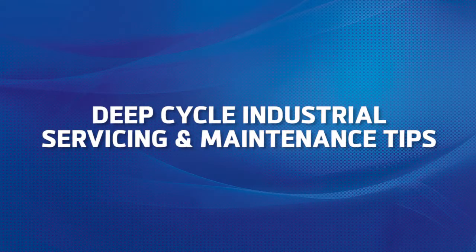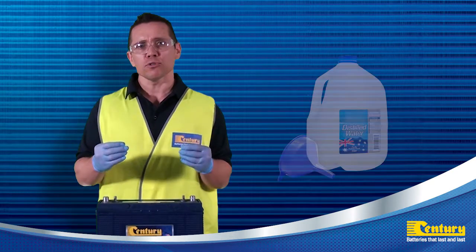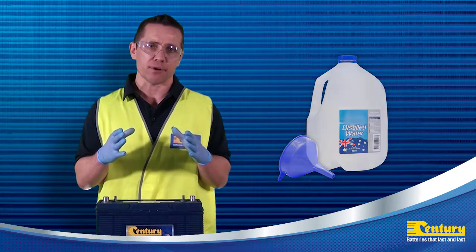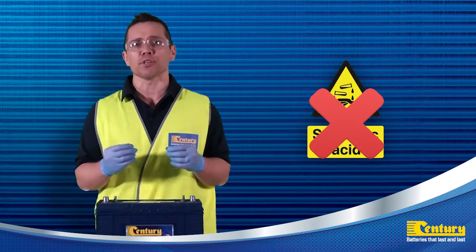I now want to share a few tips on servicing and maintaining your Century Industrial Deep Cycle batteries. When the vent plugs are removed and you notice the battery plates are exposed, top up using distilled or demineralised water to prevent contaminants from entering the battery. When topping up, never fill with sulphuric acid as this can accelerate grid corrosion, reducing battery life.